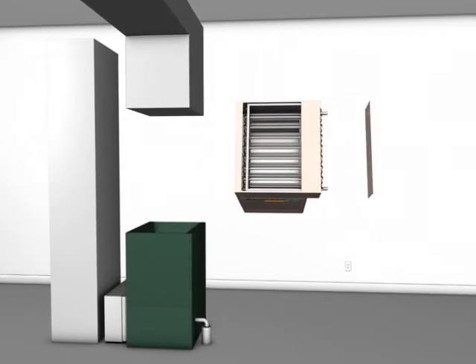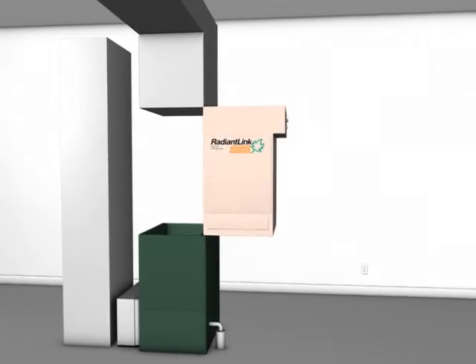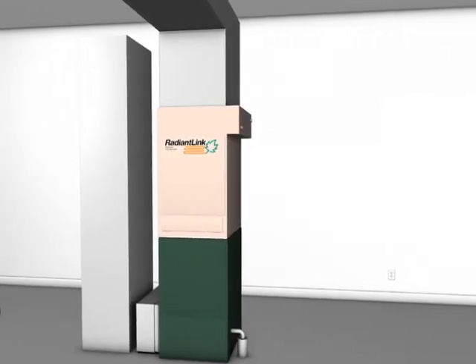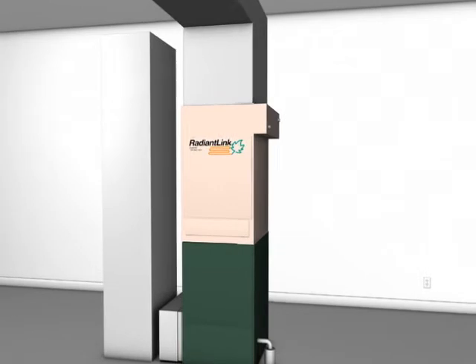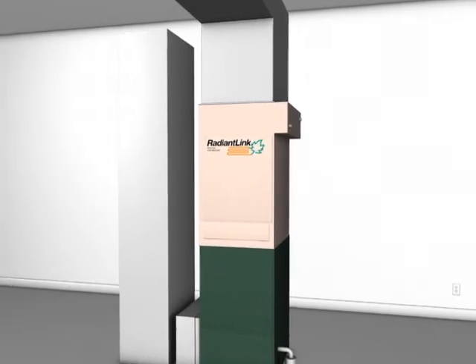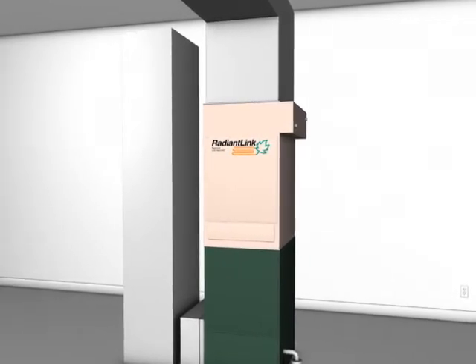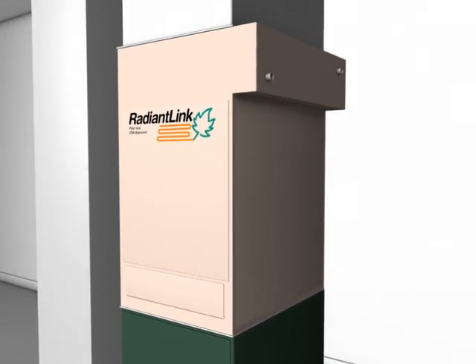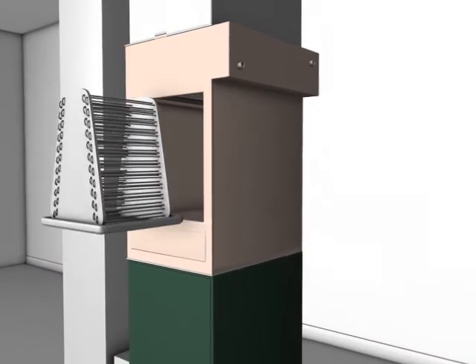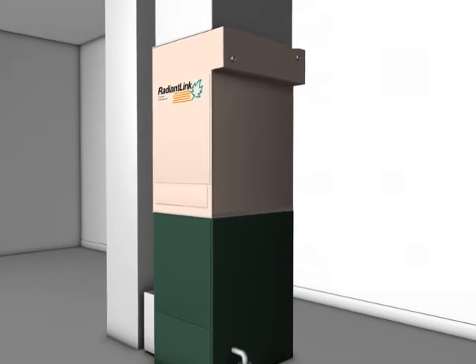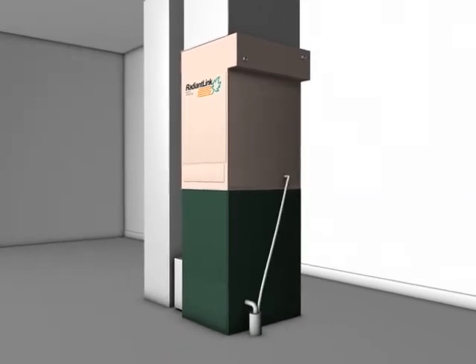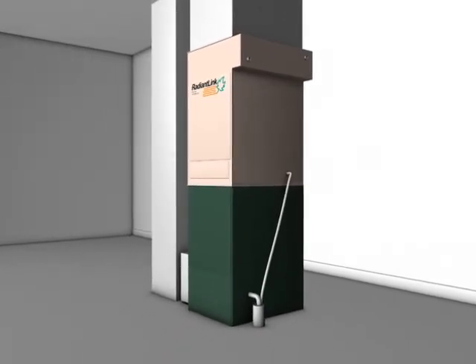Set the plenum on top of the furnace. Once the plenum is in place and the supply air ductwork is attached, silicone seal or foil tape the plenum duct connections to minimize air leakage. If air conditioning is being provided, mount the air conditioning A coil on channels inside the plenum and provide openings in the front or back of the plenum. These are the sides with the access panels for the refrigerant and drain piping.